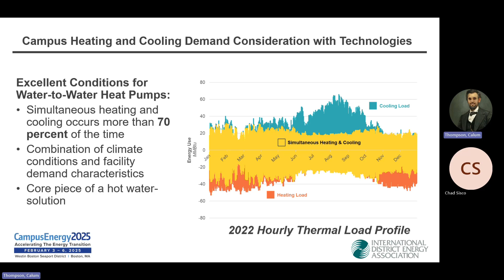And there's 24/7 demand for heating and cooling. That allowed us to look at options which leverage simultaneous heating and cooling. At UCR, we're looking at over 70% of that thermal demand being simultaneous. If we can move heat from the cooling network into the heating network, then we're not having to generate anything at all. That became a cornerstone of our technology options when it came to a hot water solution.